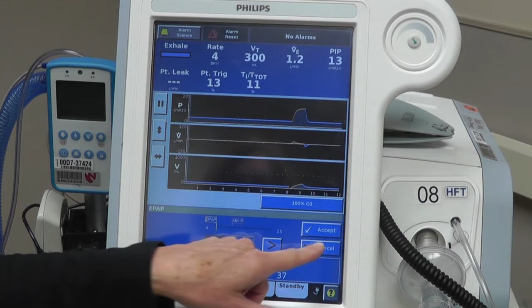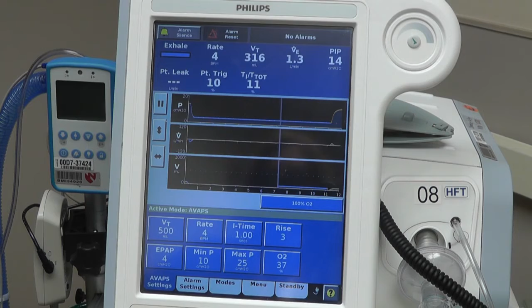So here's the other active mode, AVAPS, that you'll often see on the floor that we deliver this machine non-invasively for. You'll see the inspiratory pressure. There are 2 inspiratory pressures and an expiratory pressure. And then an average tidal volume that we're trying to target for our patient. And then there's a comfort feature here, and then a rate, just like on the spontaneous timed mode. Again, it's a backup rate, and all the breaths are going to be on their own and spontaneous.